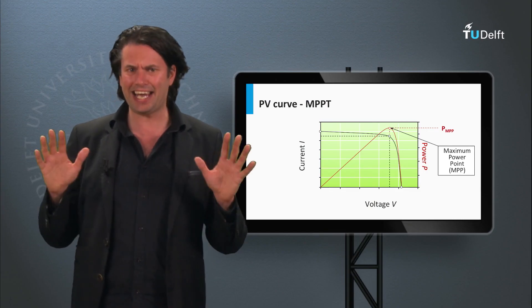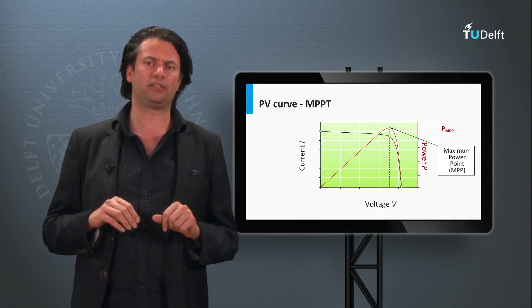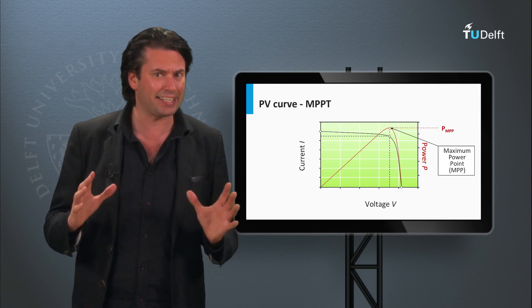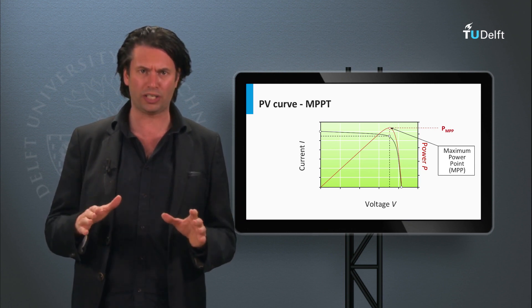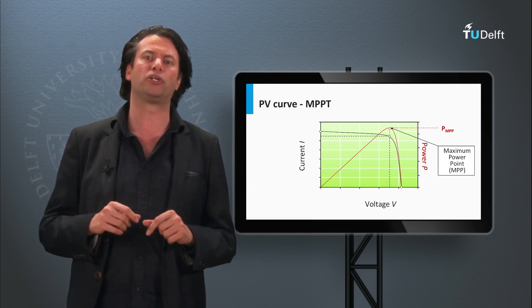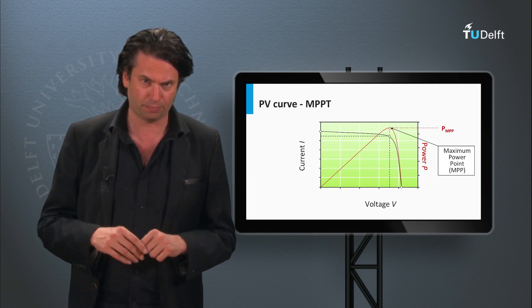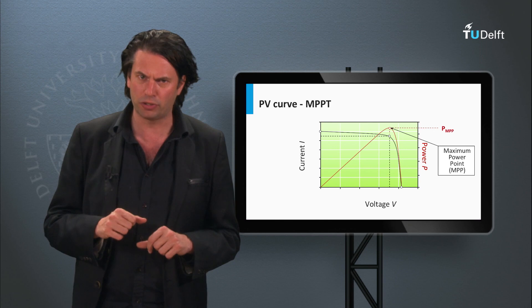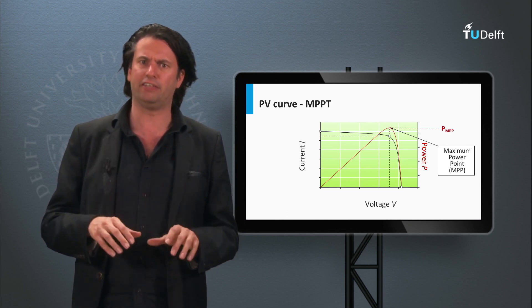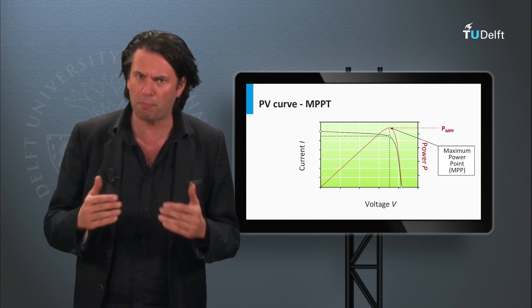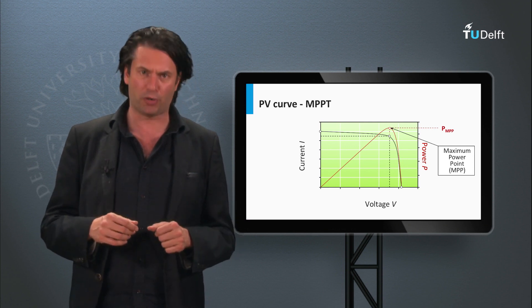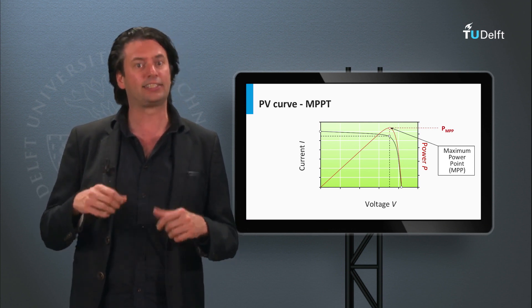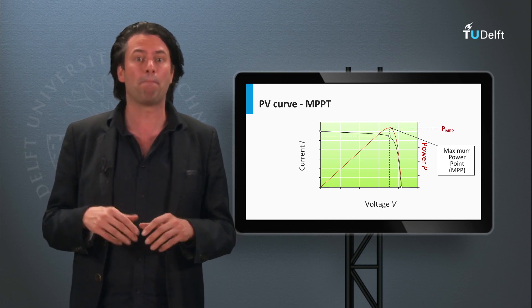Without any external electrical manipulation, the PV module's operating point is largely dictated by the electrical load seen by the PV module at its output. To get maximum power delivered by the PV module, it is therefore imperative to force the module to operate at the operating point corresponding to the maximum power, or as it is generally called, the maximum power point.